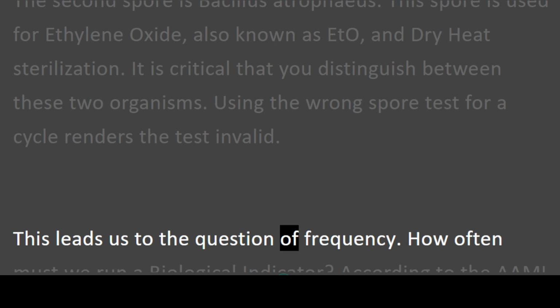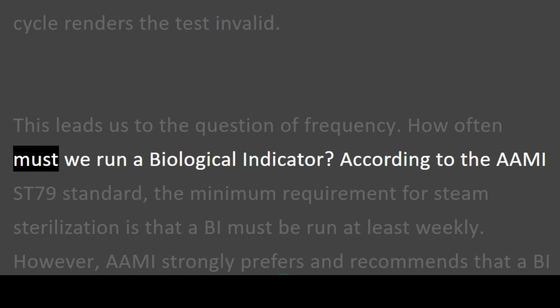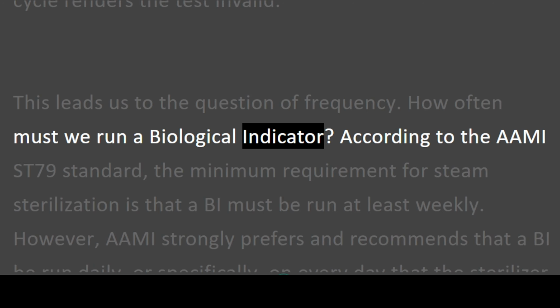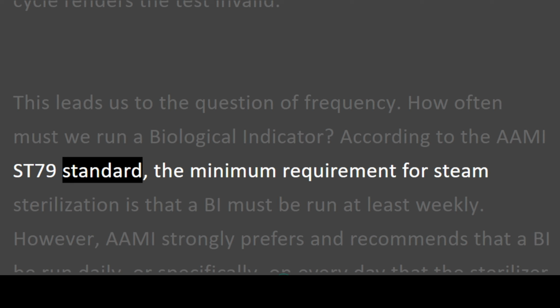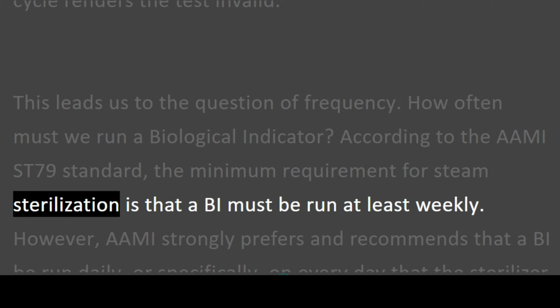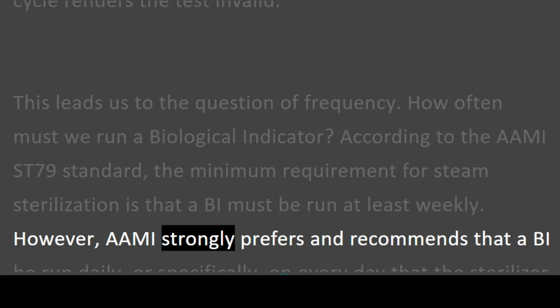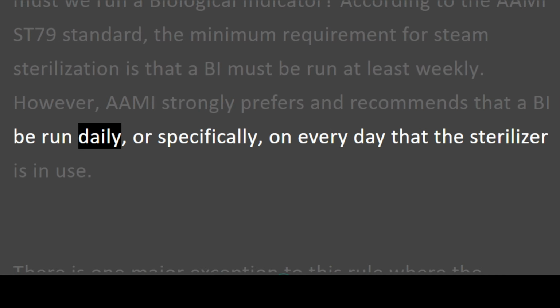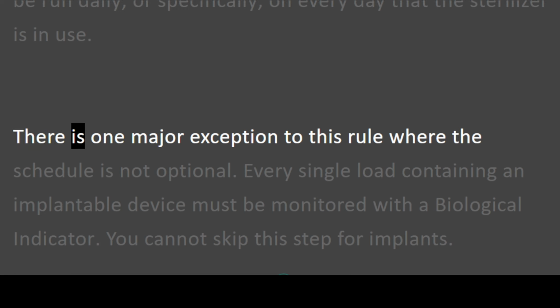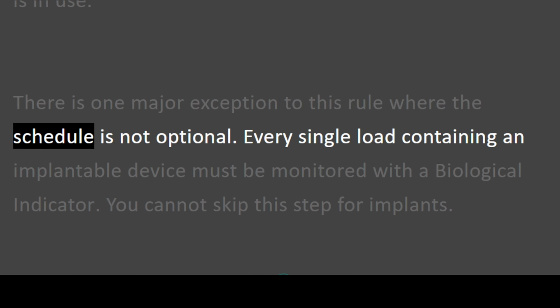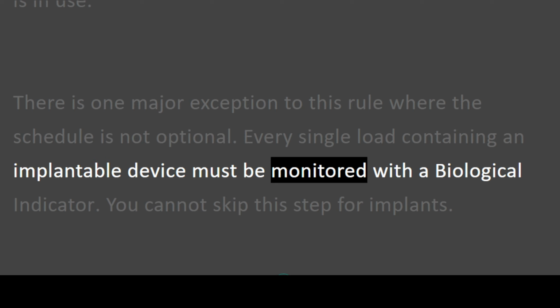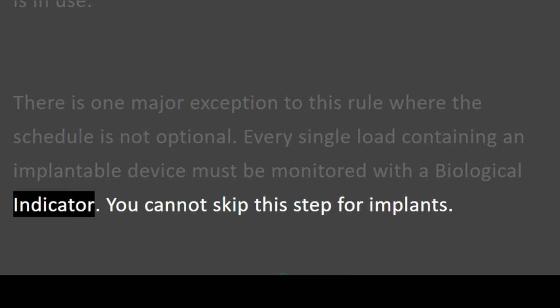This leads us to the question of frequency. How often must we run a biological indicator? According to the AAMI ST79 standard, the minimum requirement for steam sterilization is that a BI must be run at least weekly. However, AAMI strongly prefers and recommends that a BI be run daily, or specifically, on every day that the sterilizer is in use. There is one major exception to this rule where the schedule is not optional. Every single load containing an implantable device must be monitored with a biological indicator. You cannot skip this step for implants.